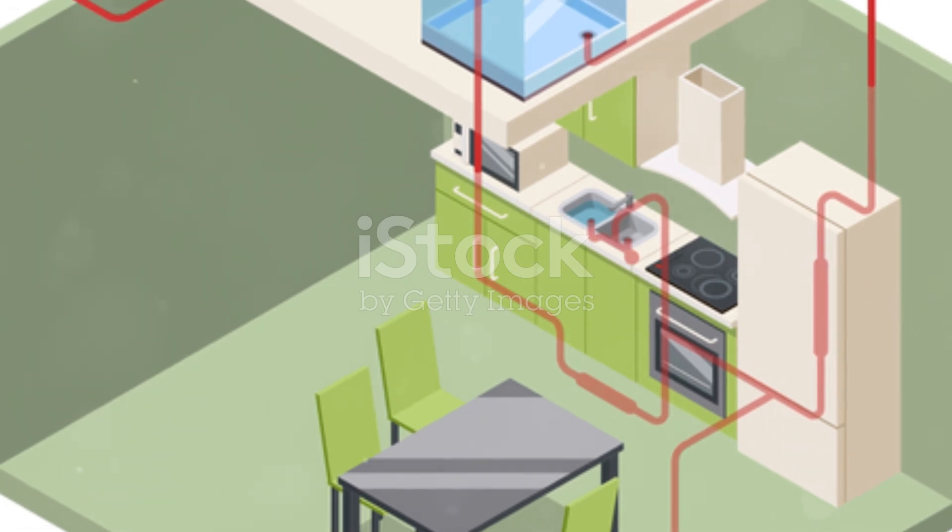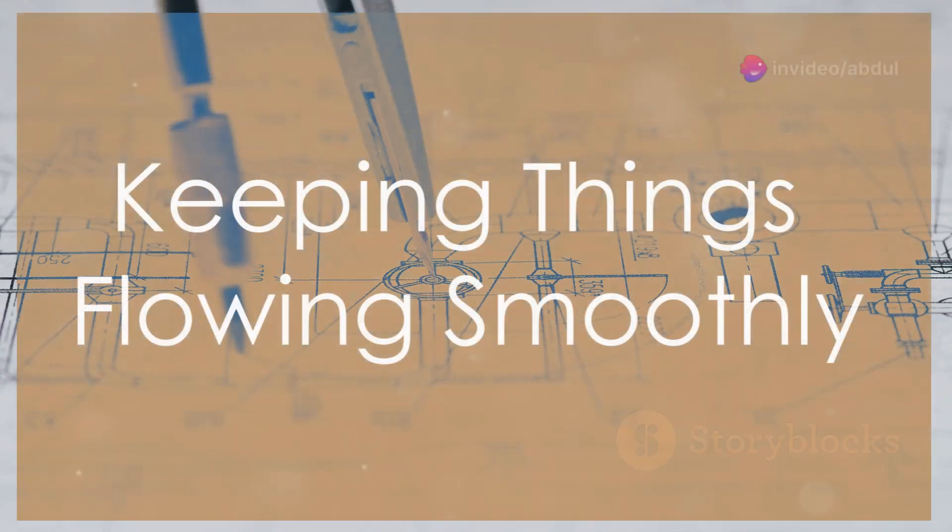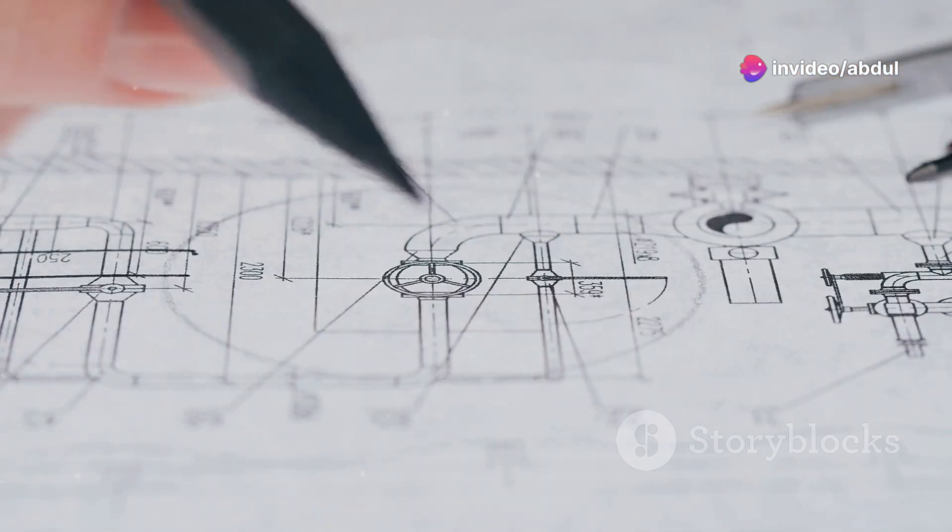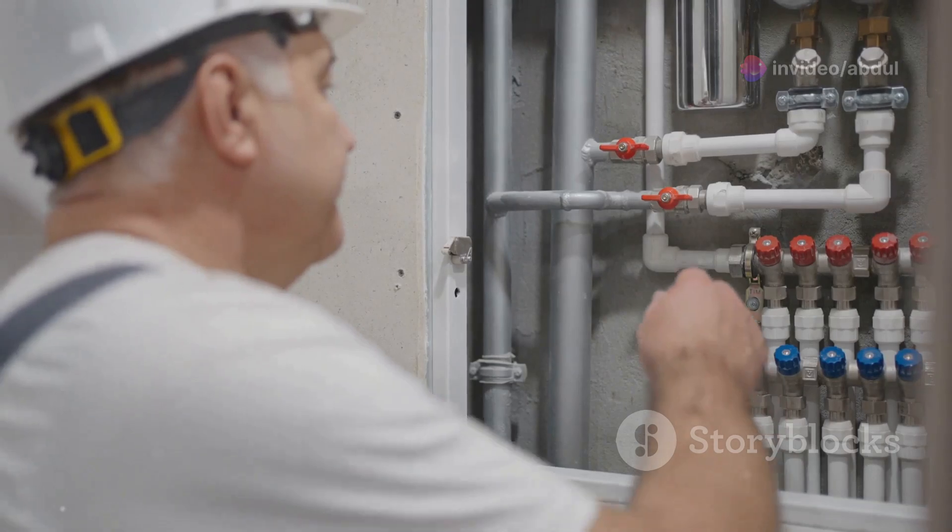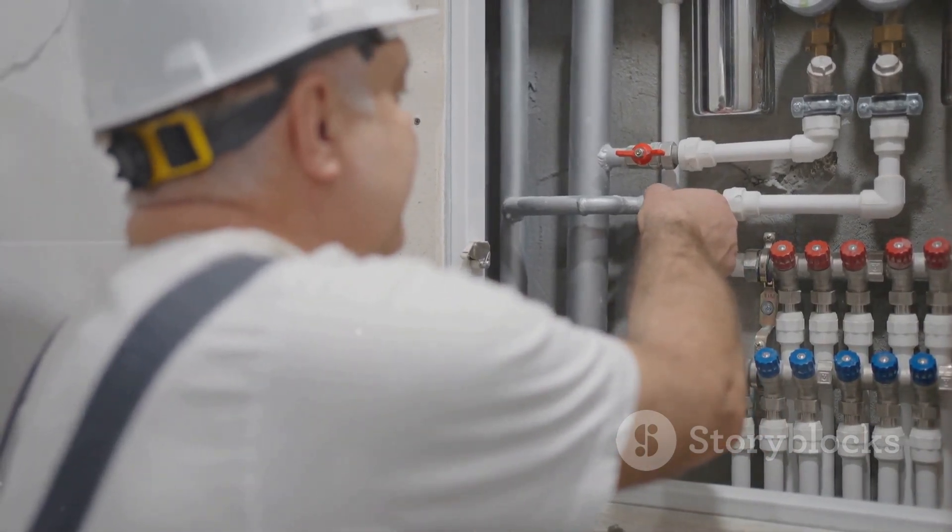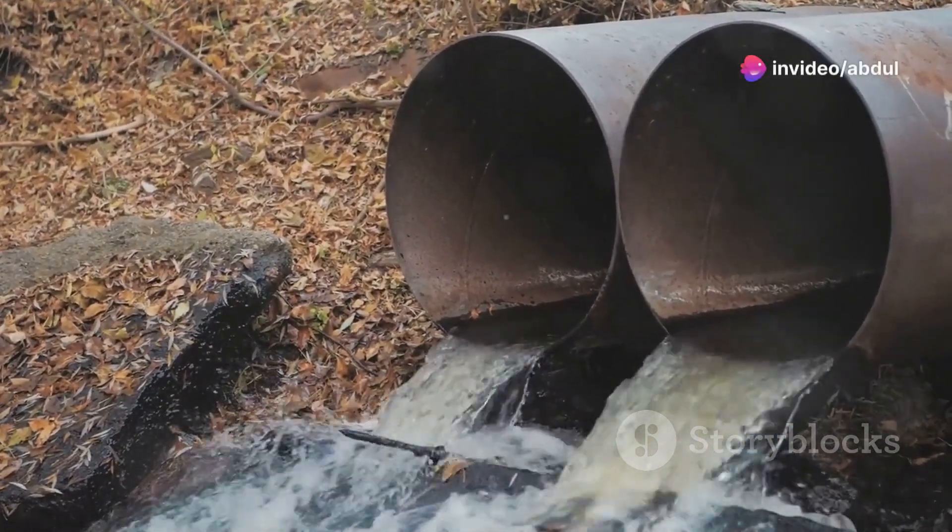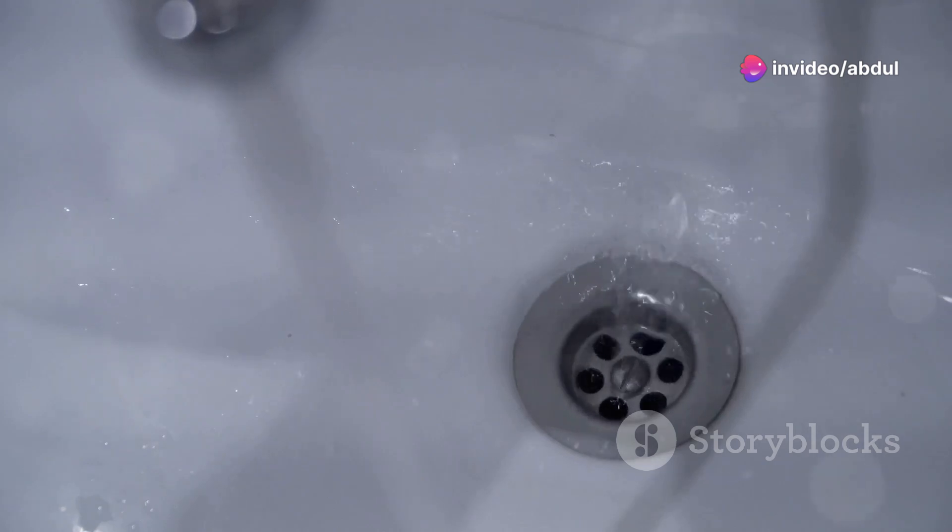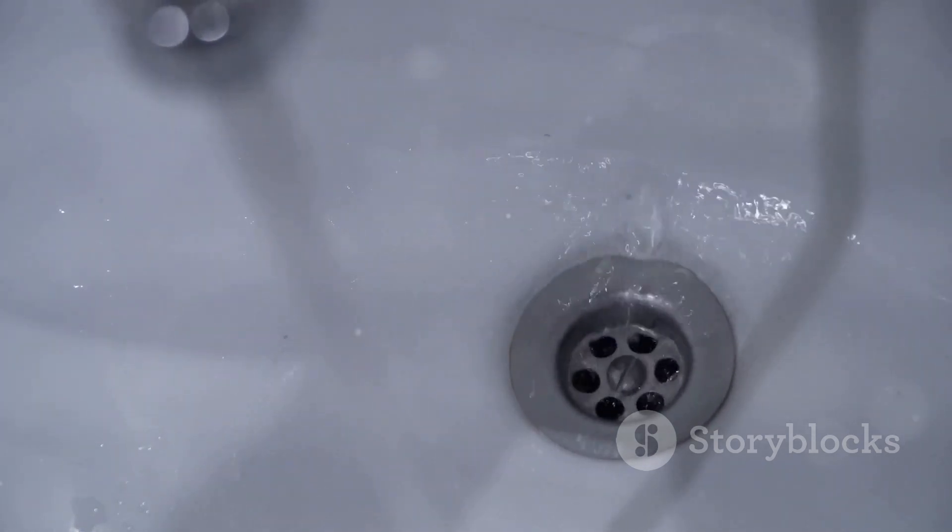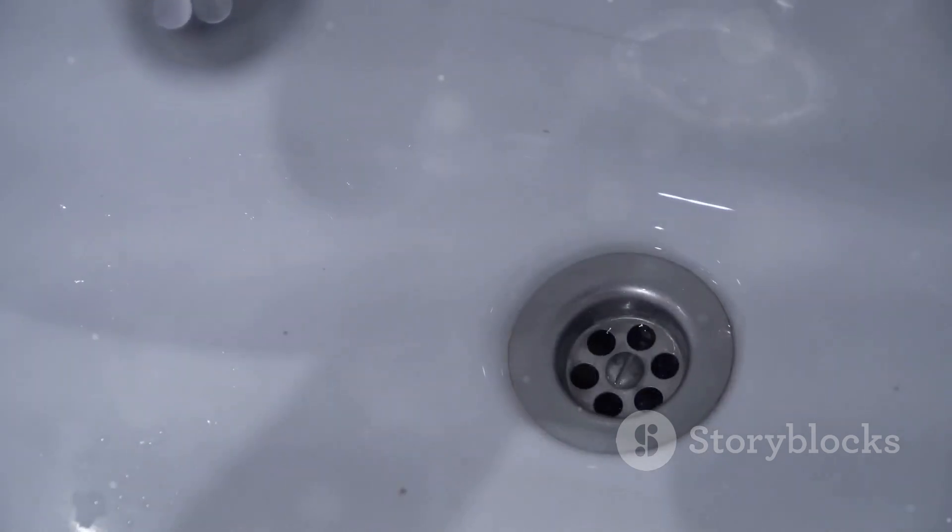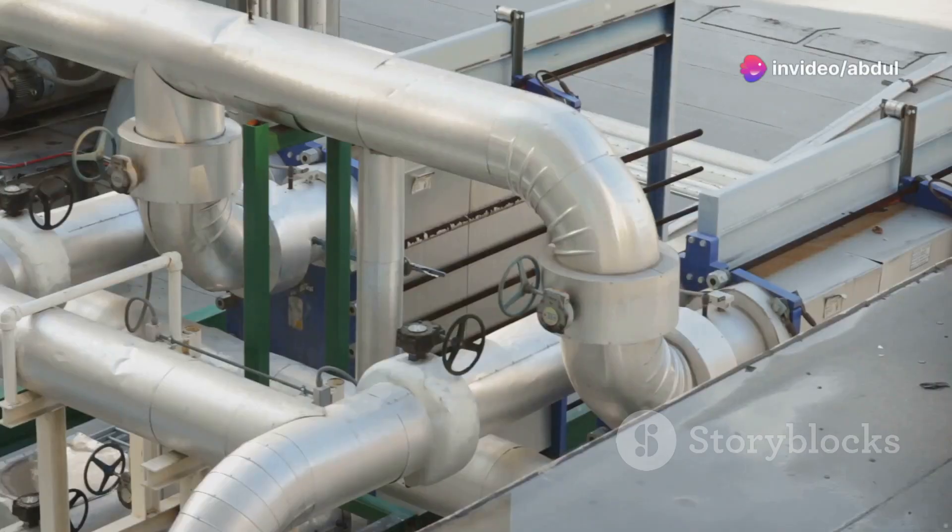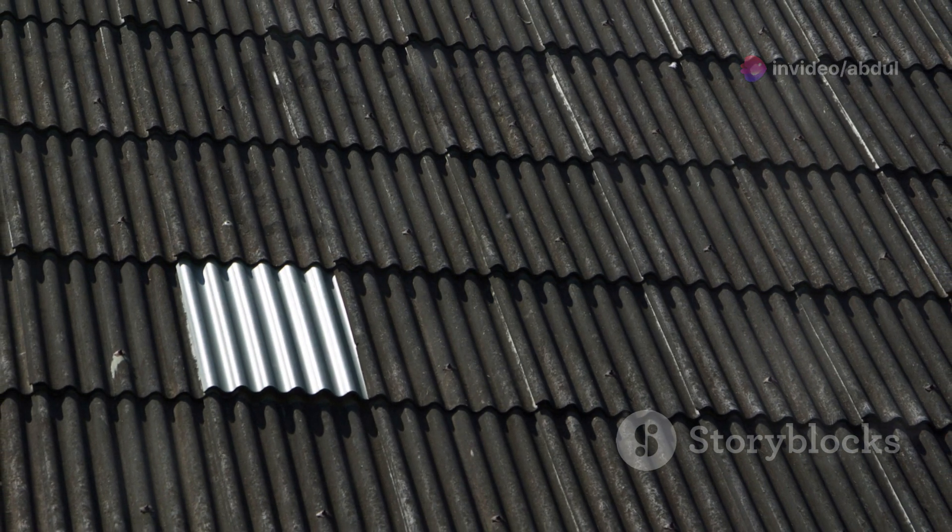Vent lines might seem mysterious, but they play a crucial role in ensuring your plumbing system functions properly. They prevent traps from being siphoned dry, allowing wastewater and sewer gases to flow smoothly. Without proper venting, you risk slow drainage, gurgling sounds, and even sewer gases backing up into your home - not a pleasant thought. When drawing vent lines, you'll generally connect them to the drain lines near fixtures and run them vertically upwards. They need to terminate above the roofline to vent gases safely outside.